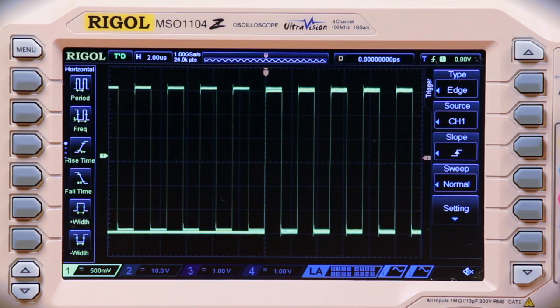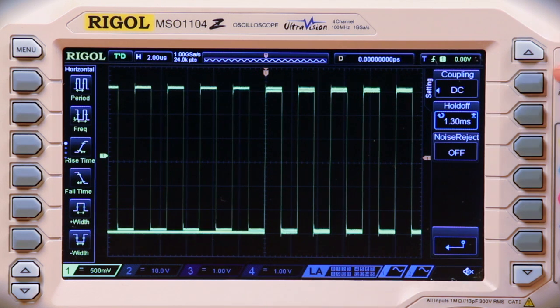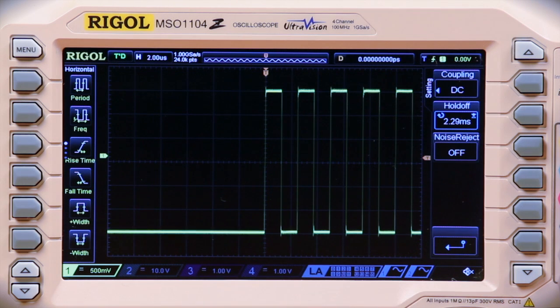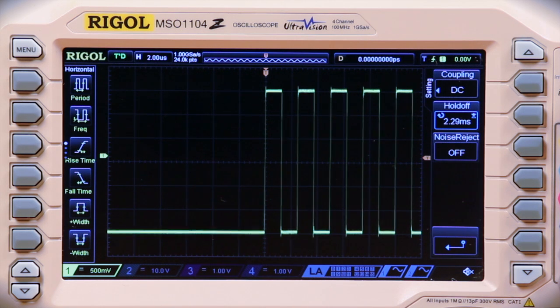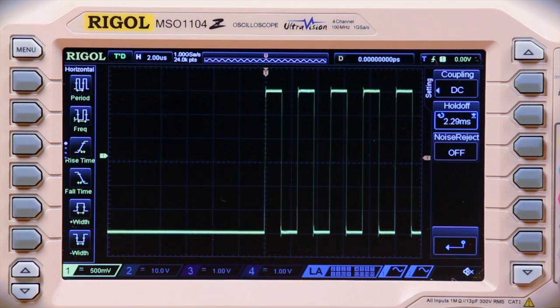Here we are looking at a series of pulses. We can use the trigger holdoff to make certain we only trigger on the first pulse. Now the trigger event is the first pulse in each pulse train, since the pulses end before the trigger holdoff expires. Each time the pulse train starts again, a new waveform is posted to the display, overlaid with the previous signals. This is how we use triggering to show how a signal changes over time, making it easy to see how many pulses are occurring in a set.